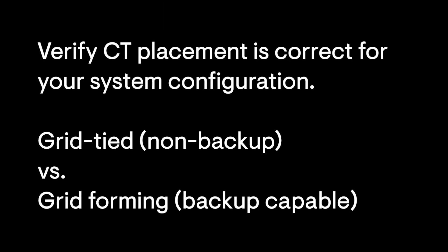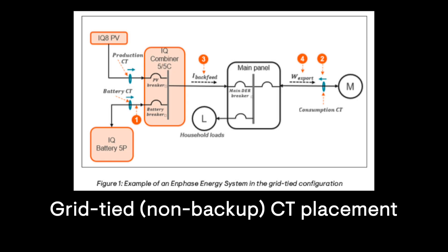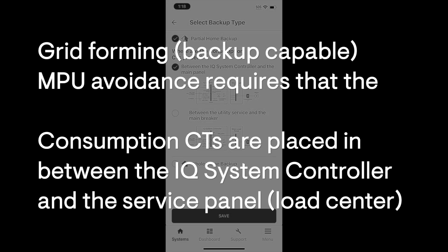Verify that the CTs are installed in the correct location as needed for your system configuration. Grid-tied, non-backup sites differ from grid-forming, backup-equipped-capable systems. In this example, we will review a grid-forming backup-capable system, starting with Main Panel Upgrade Avoidance as our objective.